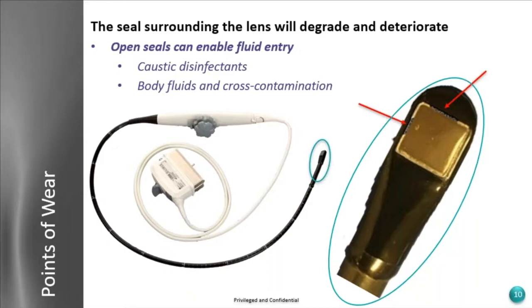So let's talk about some of the areas where that will degrade. On a transducer, there are seals around these lenses, and that is a very specific material that we research and come up with, which is compatible with the OEM recommended cleaners and disinfectants. But they do wear, and once they wear, you can see on this particular probe that material is missing. You'll get fluids in there, bodily fluids, disinfectants, and biocontaminants, so now you have a nook or cranny on this probe that traps those things.